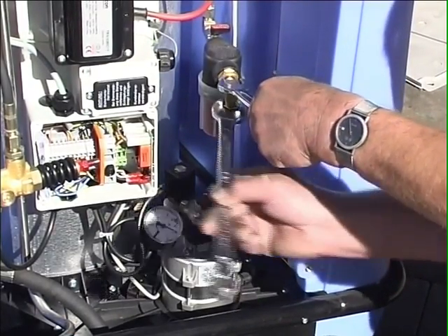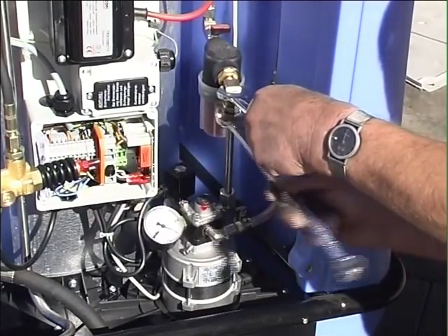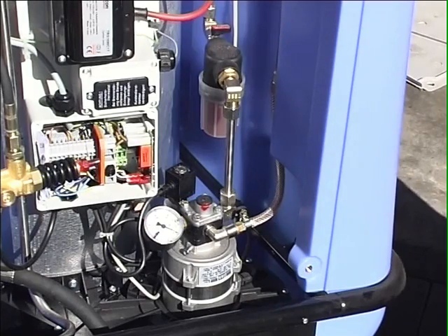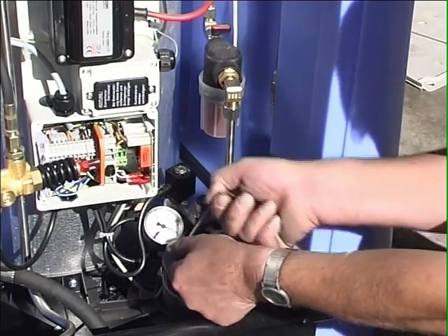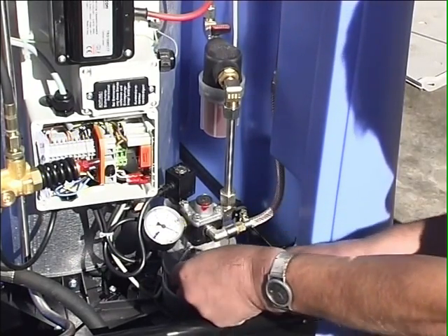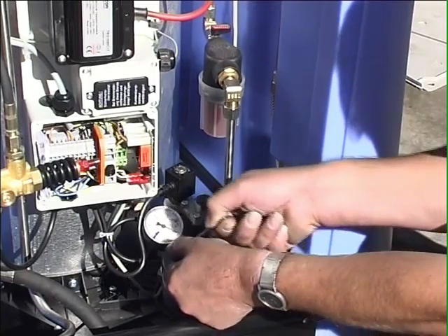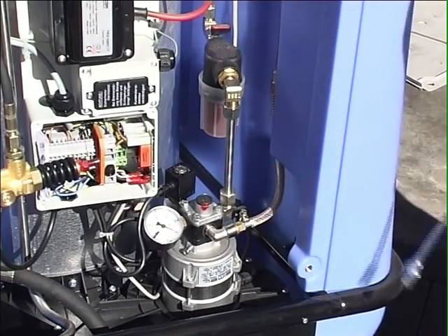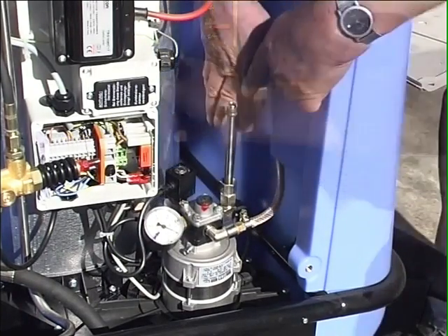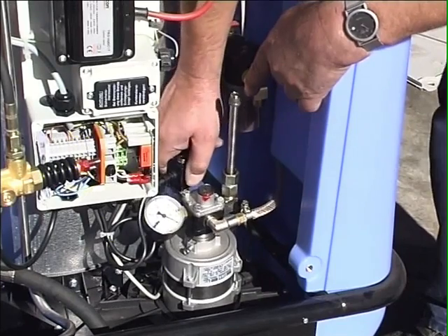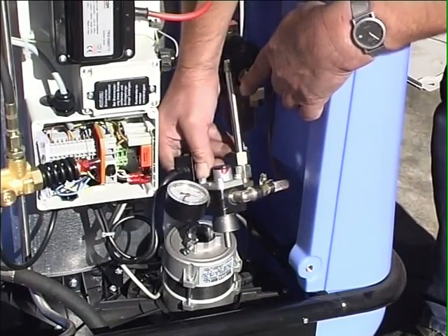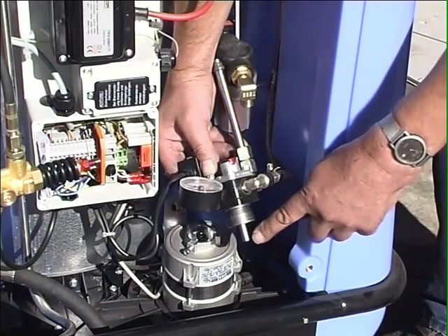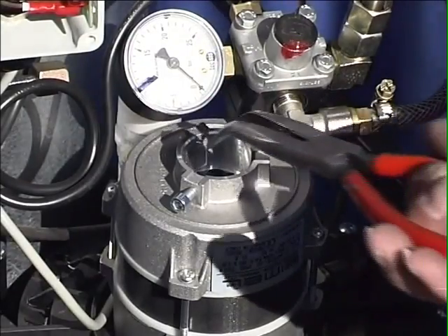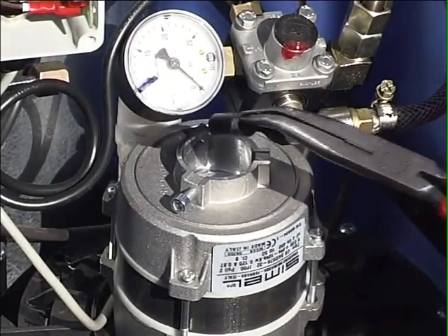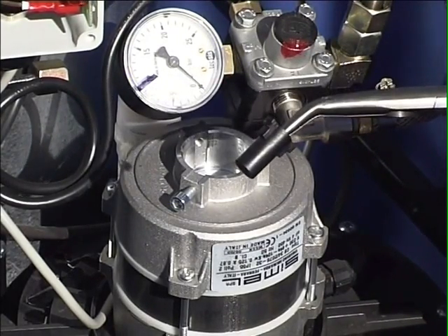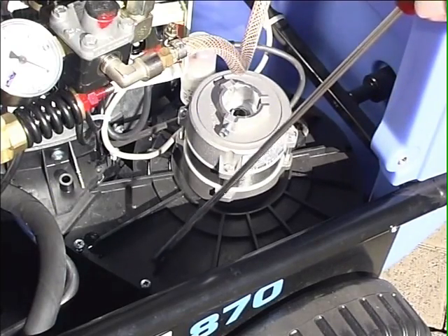Now we will show you how to remove the oil pump. Loosen the hexagon cap screws on the pump shaft and all connections. Now pull the entire pump upward. The coupling is here below, or you can use a bent-pointed plier to pull it from the plug-in connection. The fan motor with fan wheel is fixed to the fan casing with 11 screws.